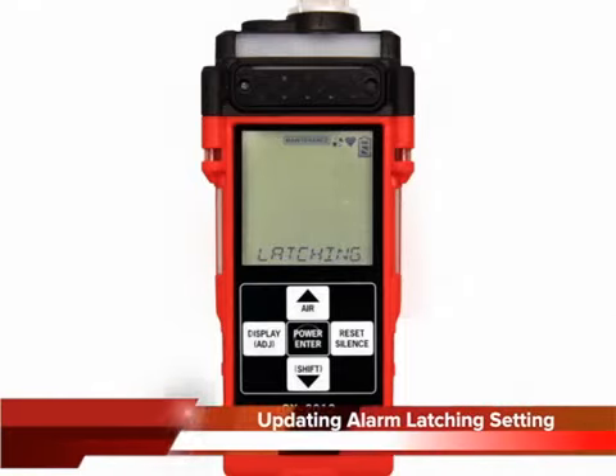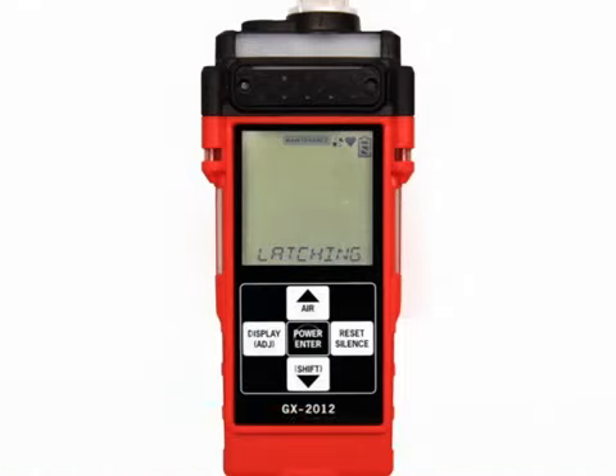With latching set to on, the default setting, the GX 2012 remains in alarm condition until the alarm condition passes and the power enter button is pressed. With latching set to off, the GX 2012 automatically resets an alarm when the alarm condition passes.